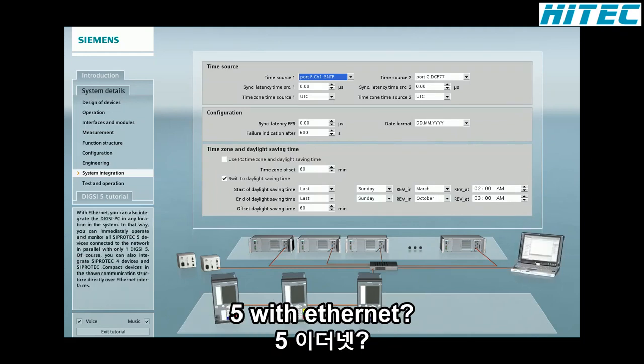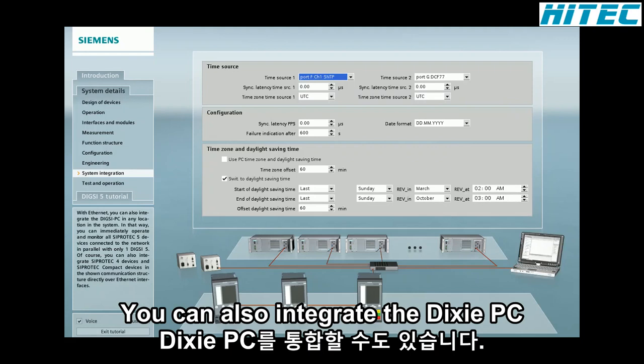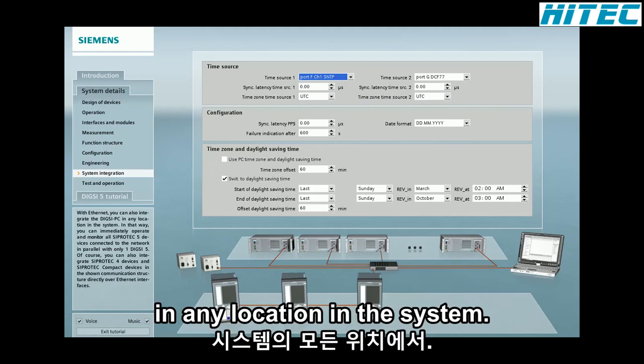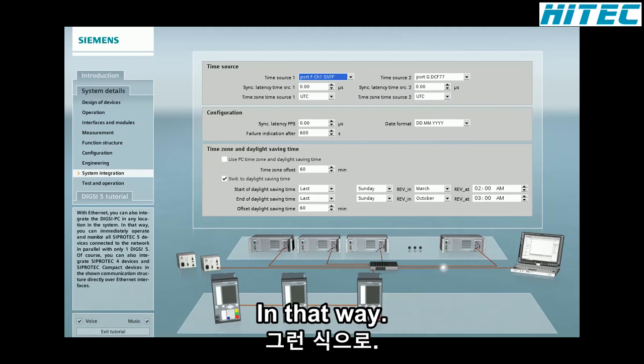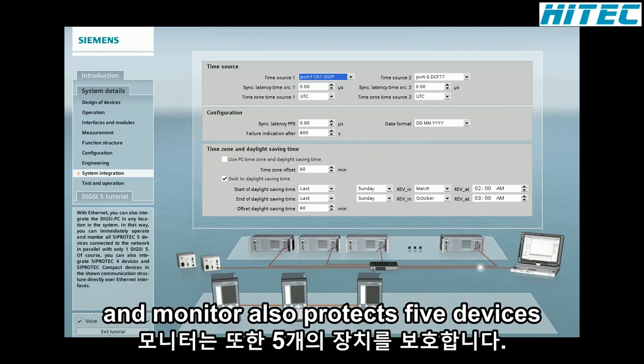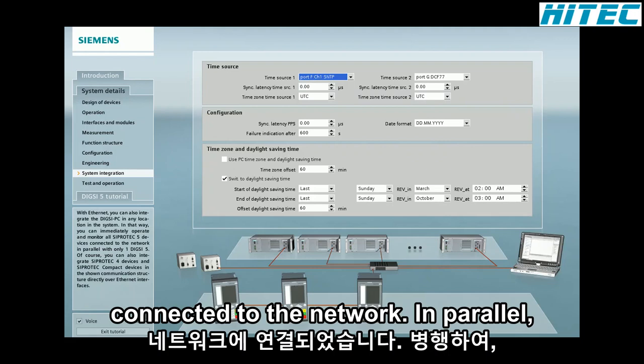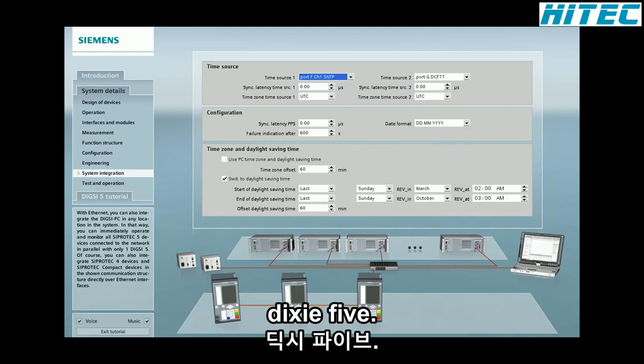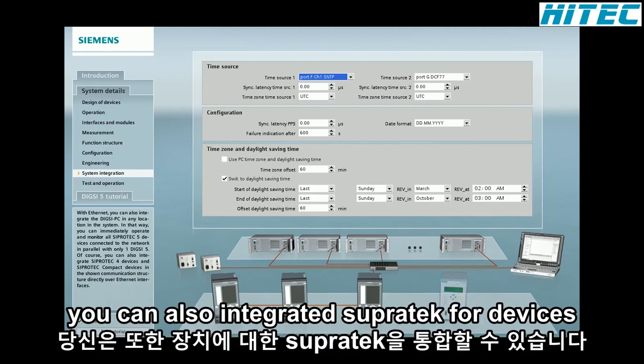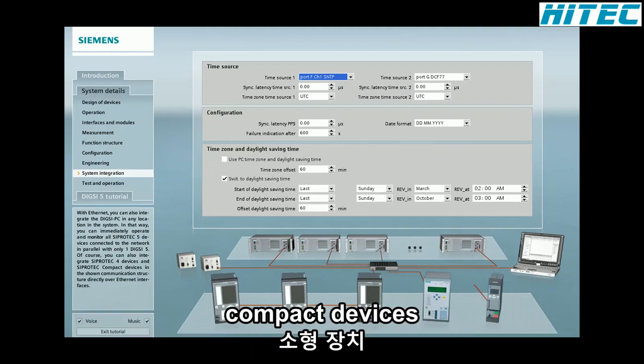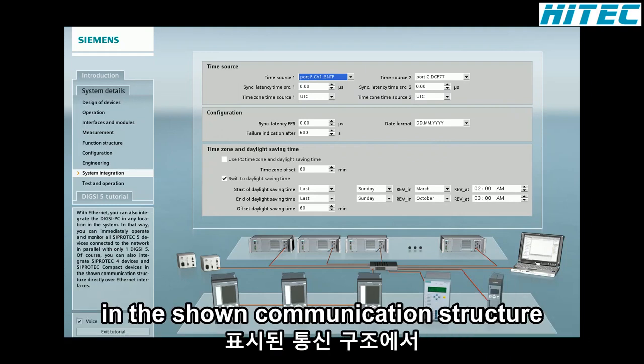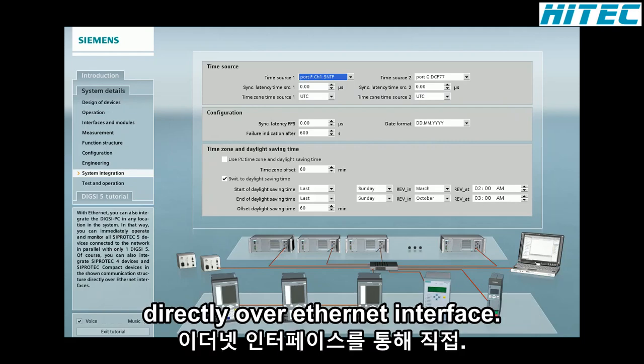With Ethernet, you can also integrate the DIGSI PC in any location in the system. In that way, you can immediately operate and monitor all SIPROTEC 5 devices connected to the network in parallel with only one DIGSI 5. Of course, you can also integrate SIPROTEC 4 devices and SIPROTEC compact devices in the shown communication structure directly over Ethernet interfaces.